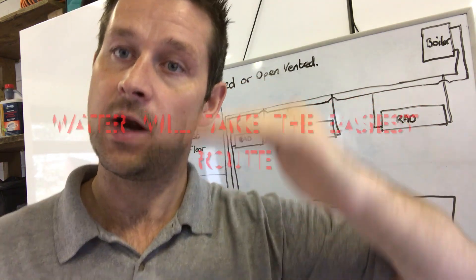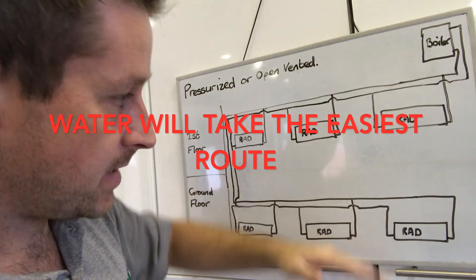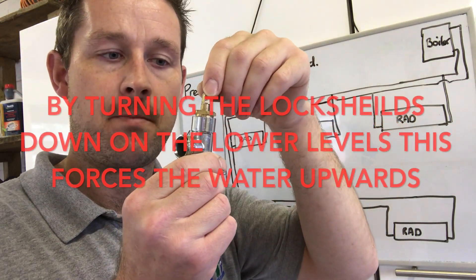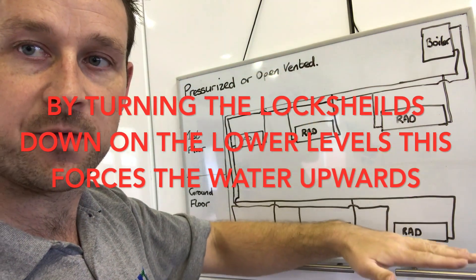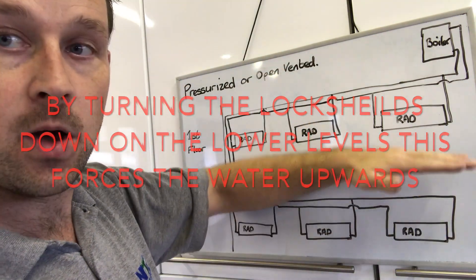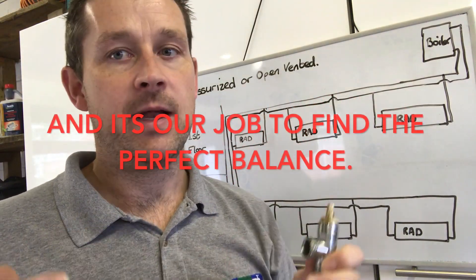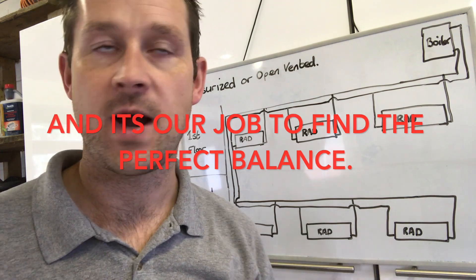What we've got to do is the downstairs radiators, we actually turn these down so that we've only got a trickle of water coming through downstairs, and the upstairs we open up more. Generally, the best practice to start with, if you're having a problem with a radiator or a new installation, do all the downstairs radiators.